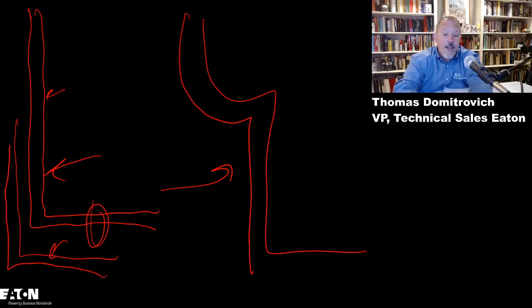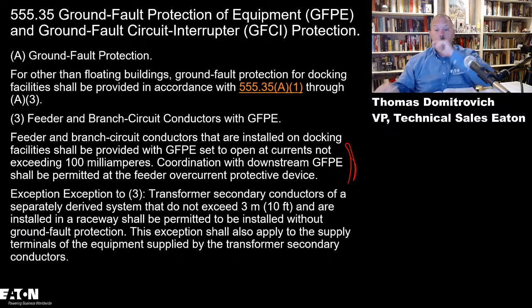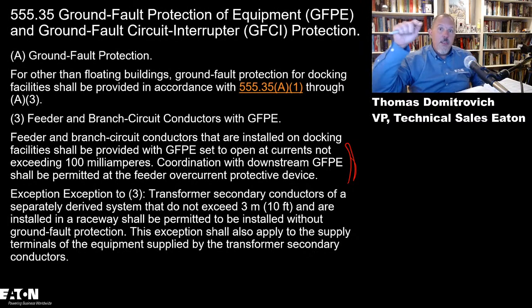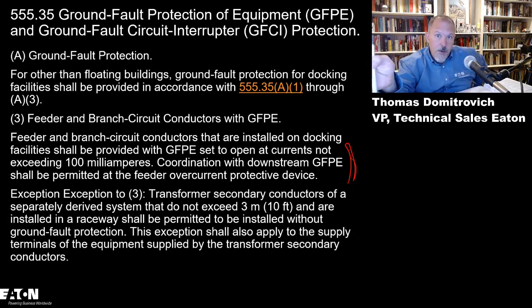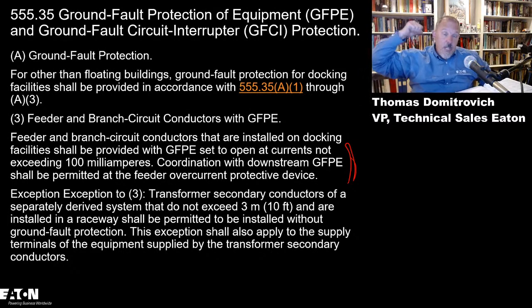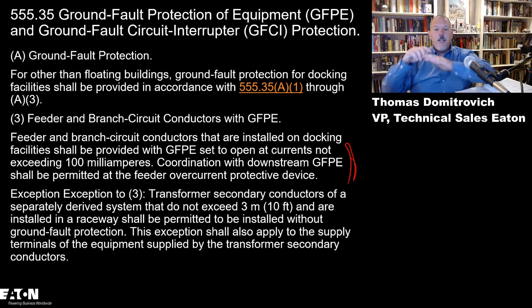It will have a curve, and I can add some intentional delays to get a level of coordination. So if one boat plugs in and he draws 5 amps, if I don't have coordination, I'll trip all of my ground fault protection of equipment upstream. If I have this coordination, then I could have it so that my 30 milliamp molded case breaker in the pedestal takes only that boat out, while the main or the feeder protection has a slight delay. So that's sort of what we did in the ground fault protection.